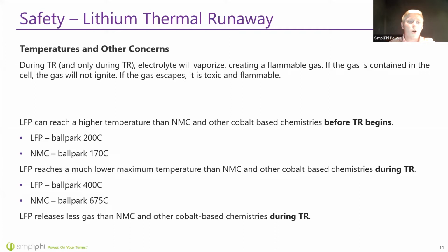Lithium iron phosphate also reaches a much lower maximum temperature than NMC and other cobalt-based chemistries during a thermal runaway event. Even in the worst case scenario, LFP will reach a maximum of around 400 Celsius, whereas NMC and other cobalt-based batteries will reach around 675 degrees Celsius. Finally, lithium iron phosphate releases less gas than other cobalt-based chemistries during thermal runaway.